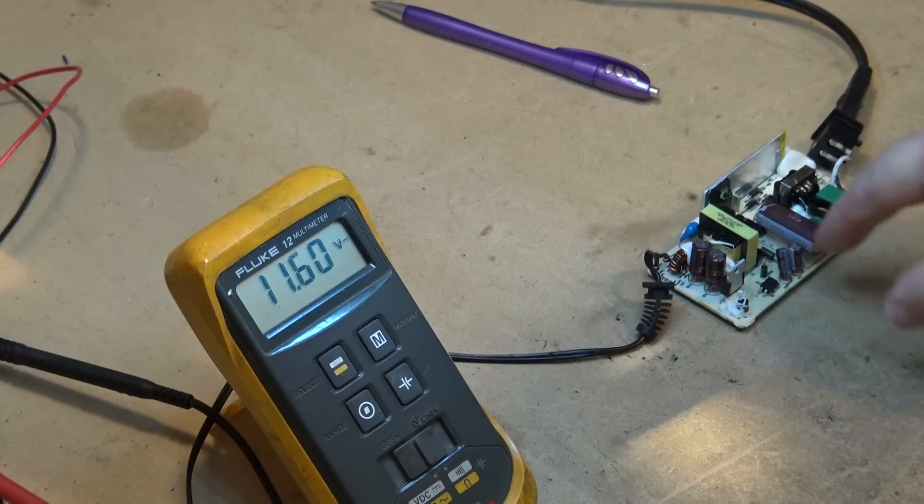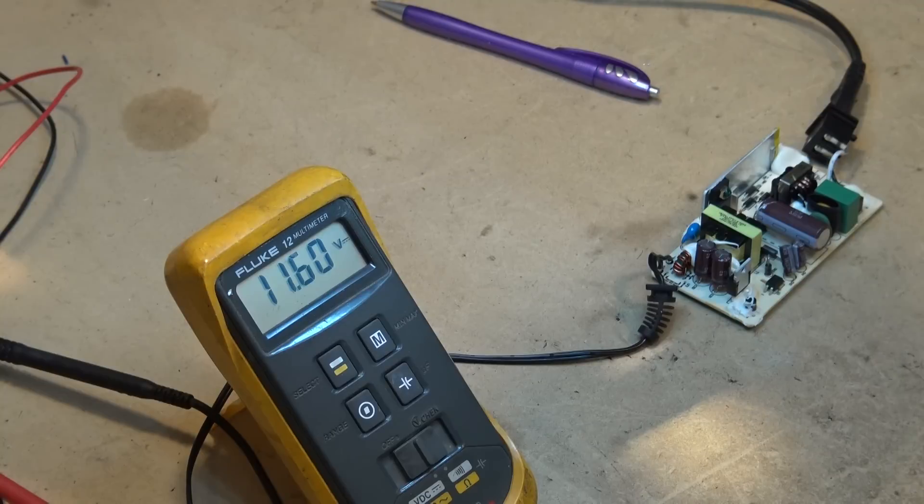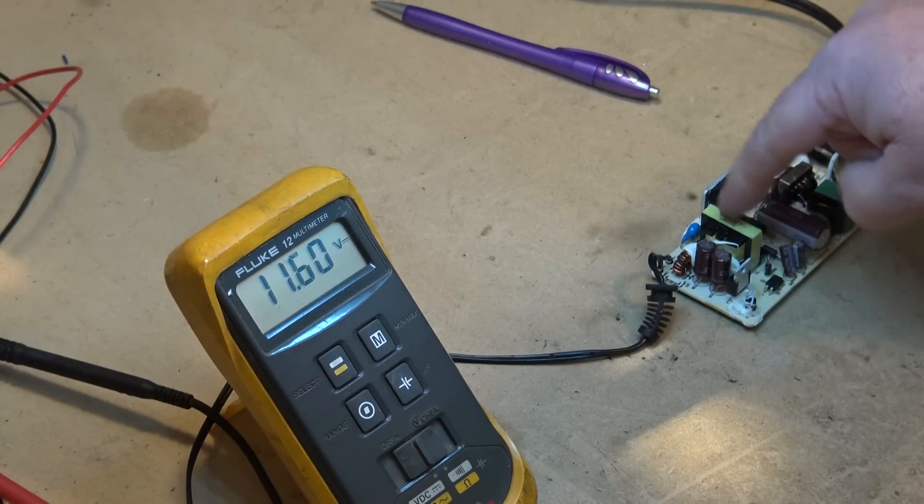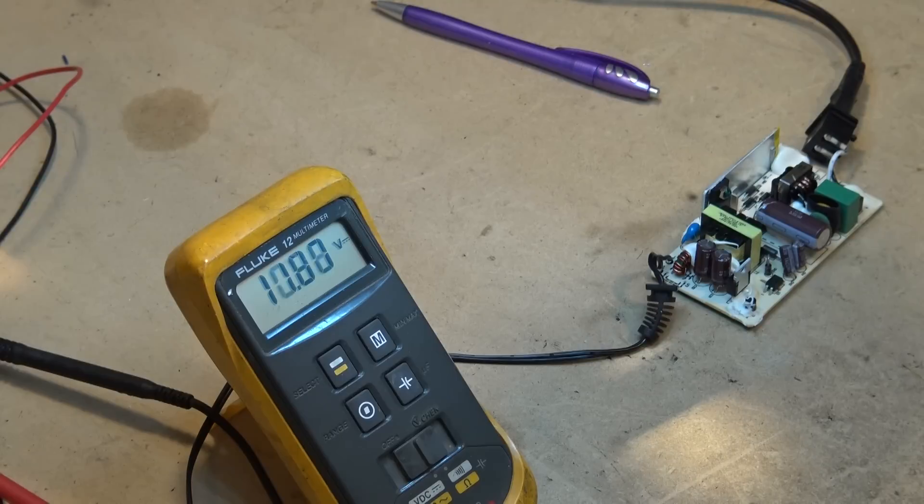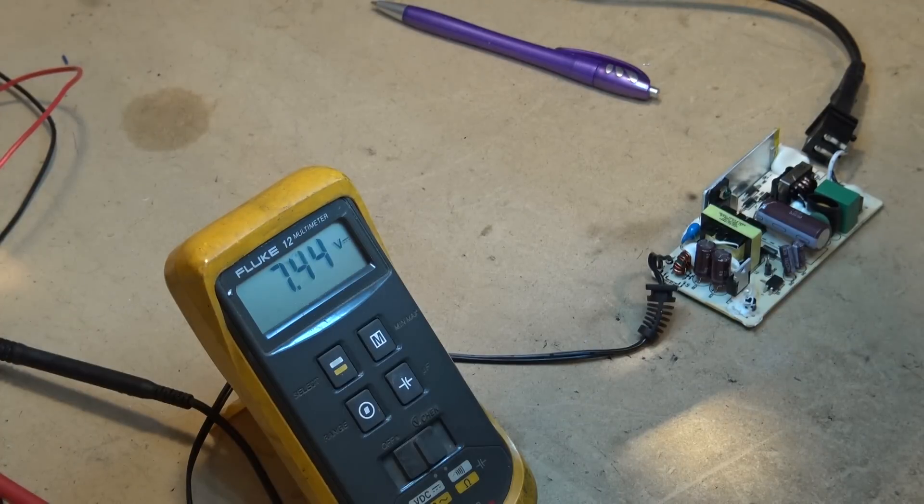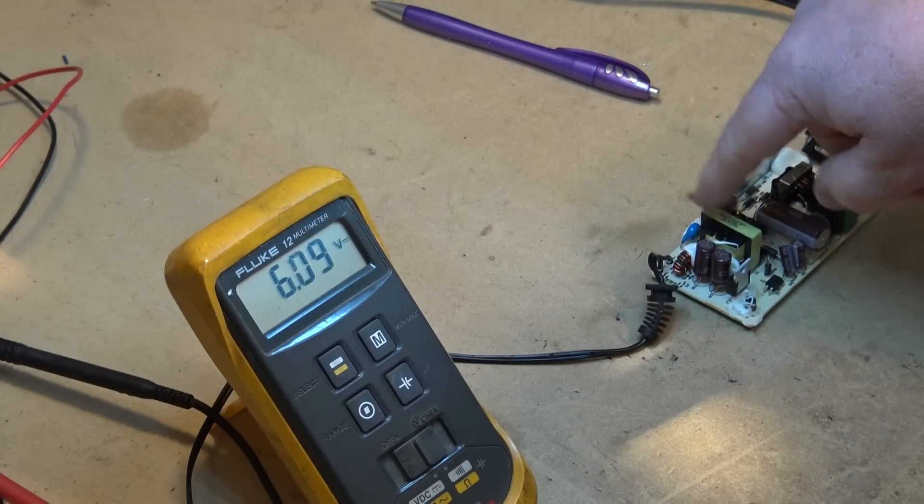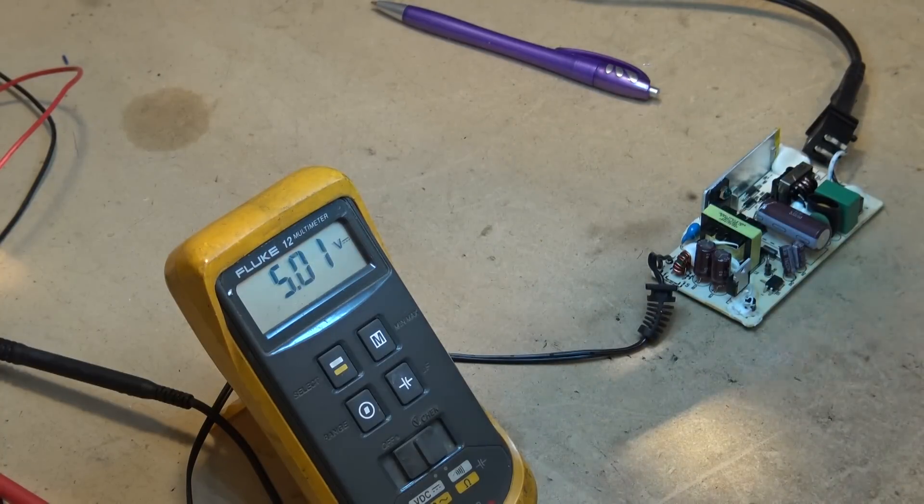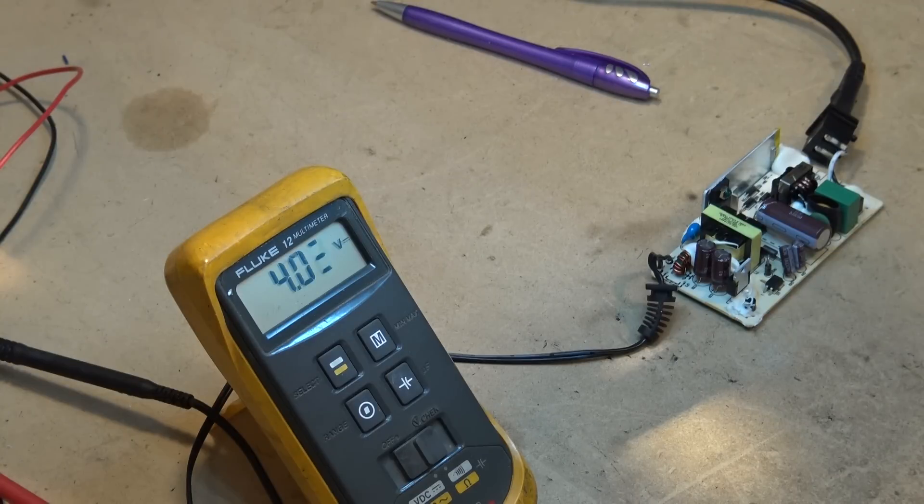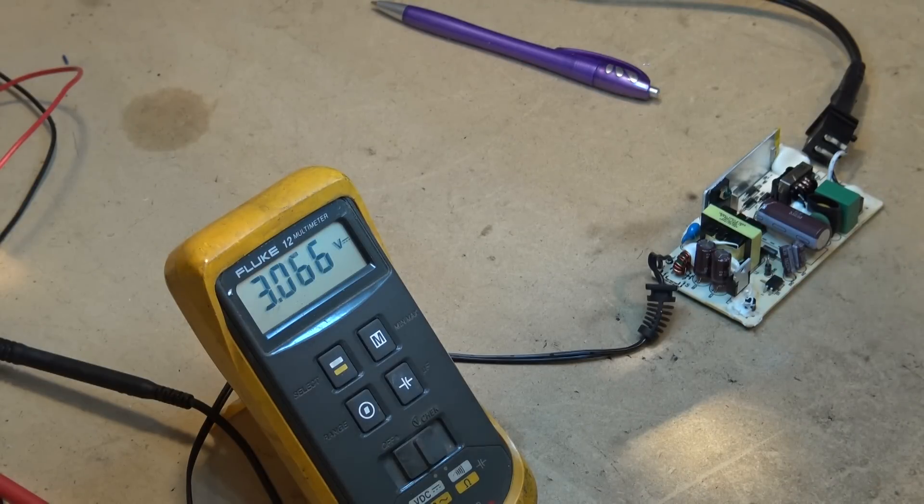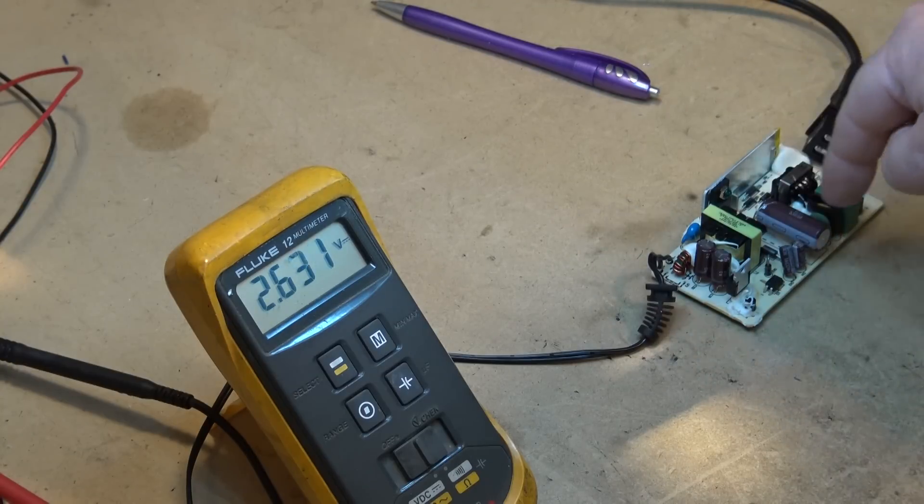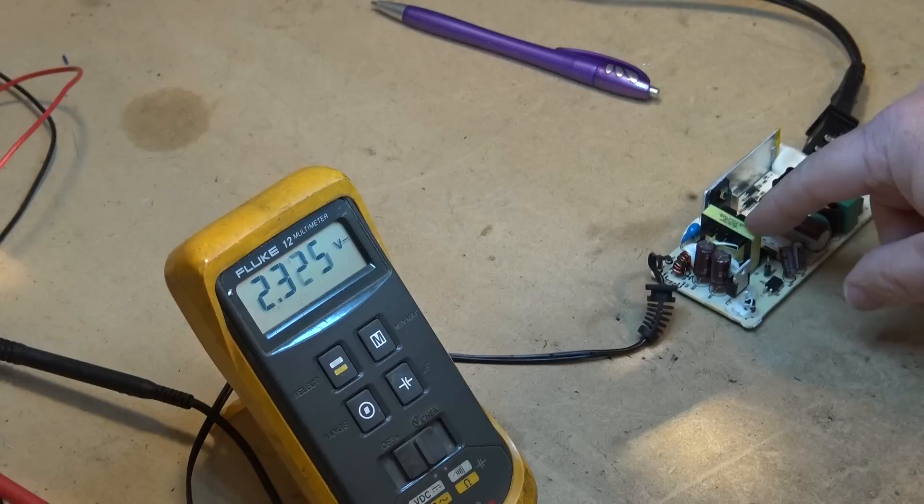...that warned us about failing capacitors in the switching power supplies. And it was in the primary side with some of the oscillator capacitors like down here. And what was happening was they were causing the frequency to shift up. And on the original design they were set to operate below the resonant frequency. How these things work is they can change the duty cycle or they change the frequency. And how the Panasonic ones worked was they worked on the basis that a transformer becomes more efficient when it gets to the resonant frequency. So what they would do is - say the resonant frequency was around 70 kilohertz - they were running them down at maybe 60 kilohertz. And to increase the voltage they would increase the frequency to 65 or 66 kilohertz. And to drop the voltage they would decrease the frequency and take the transformer further away from resonance. And what was happening was as a couple small capacitors - they're like one microfarad, 160 volt - when they dried up...